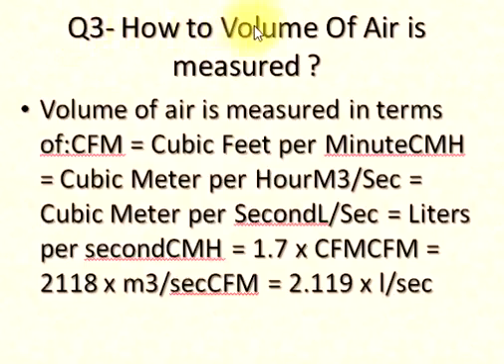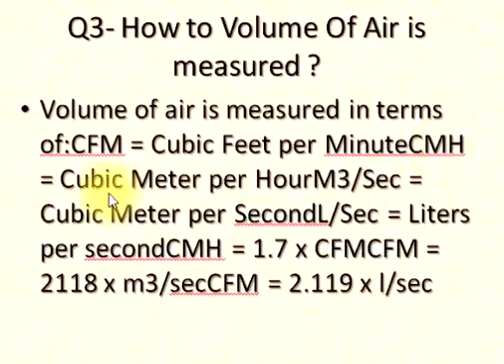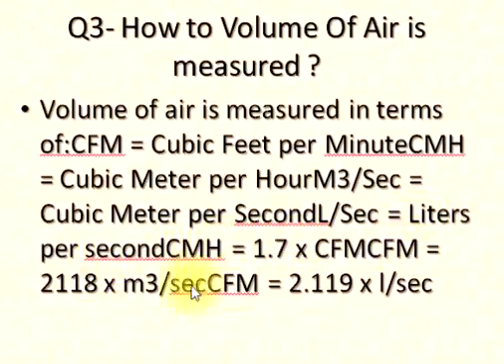Q3: How is the volume of air measured? Volume of air is measured in terms of: CFM = cubic feet per minute; CMH = cubic meter per hour; M3/s = cubic meter per second; L/s = liters per second. CMH = 1.7 × CFM; CFM = 2,118 × M3/s; CFM = 2.119 × L/s.